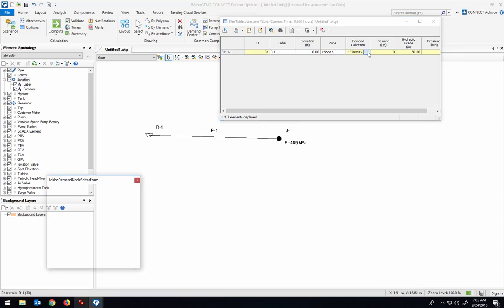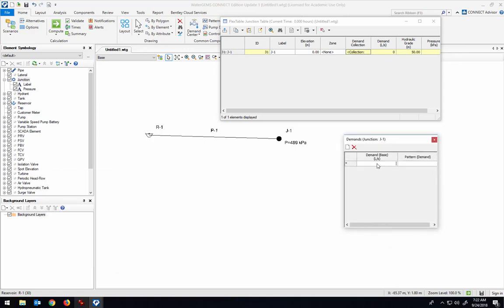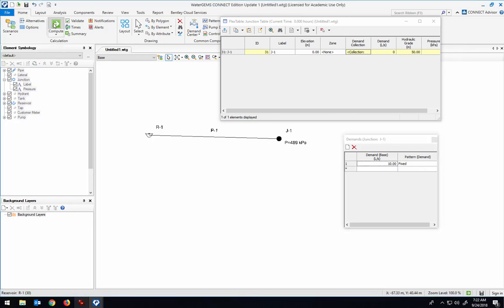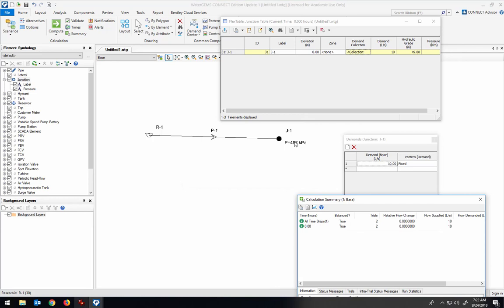So now let me specify that the demand through there is 10 liters per second. Now, it hasn't changed the pressure yet because I need to recompute again. And once I do, you'll notice the pressure's a little bit lower.